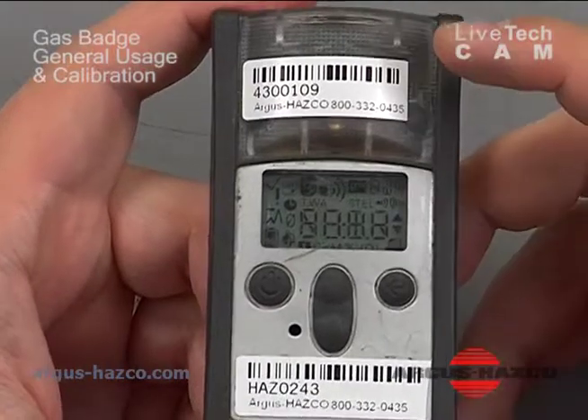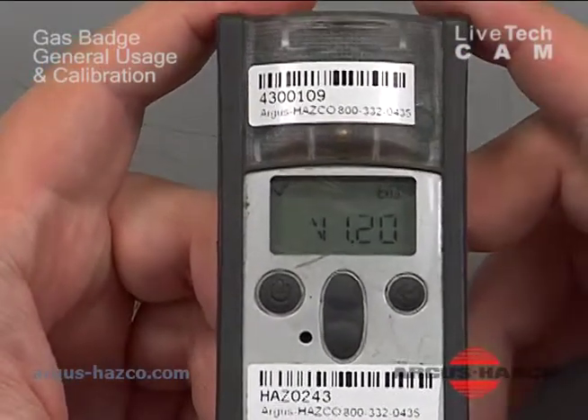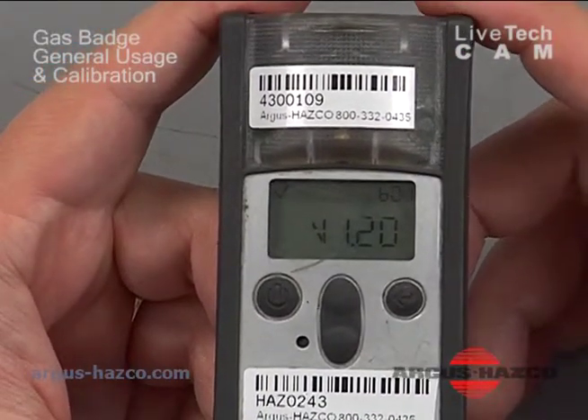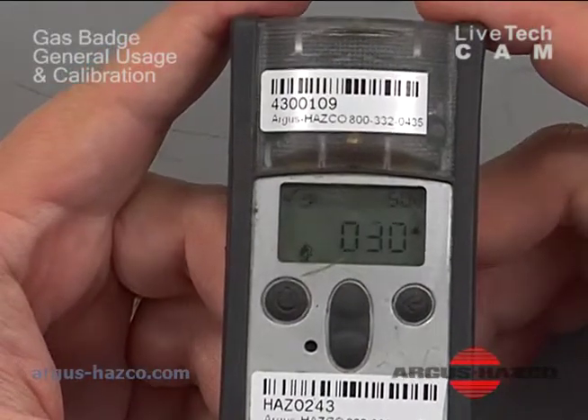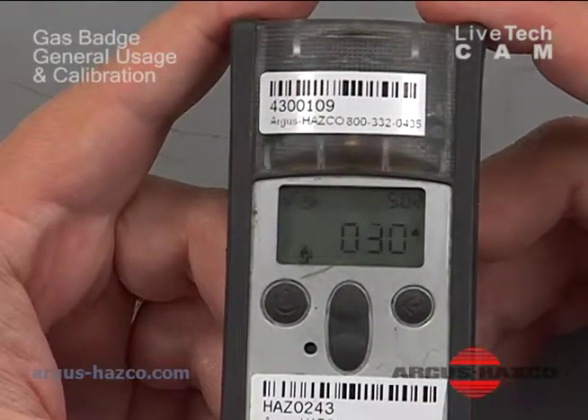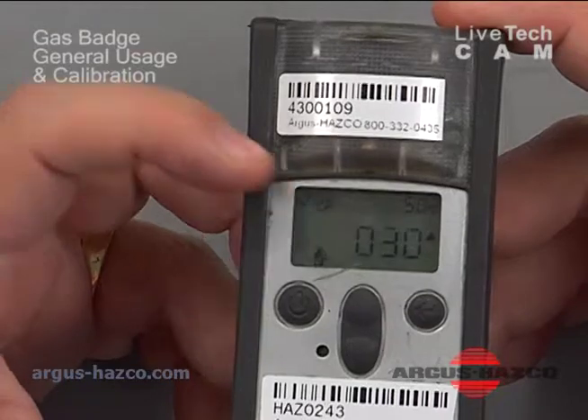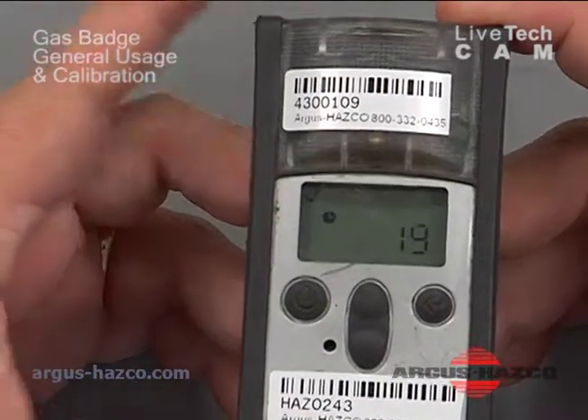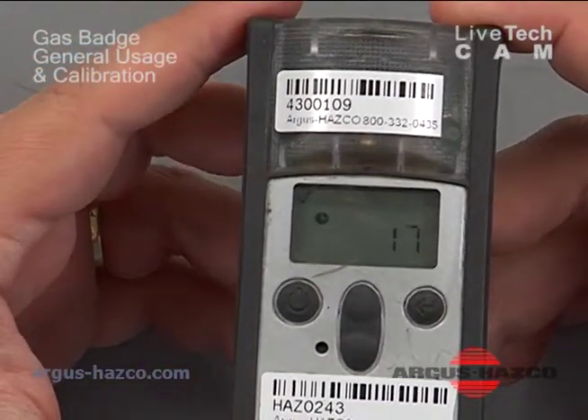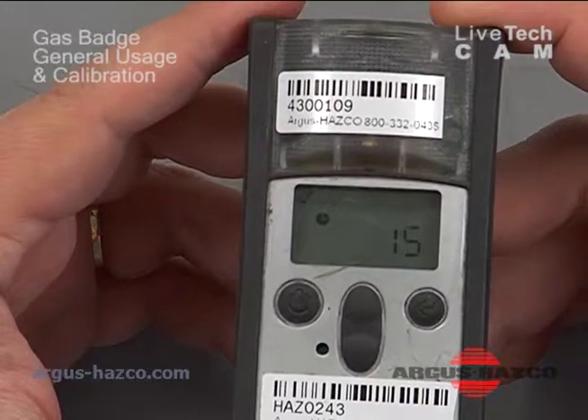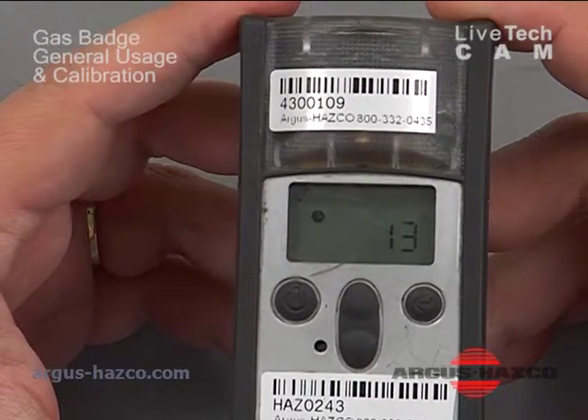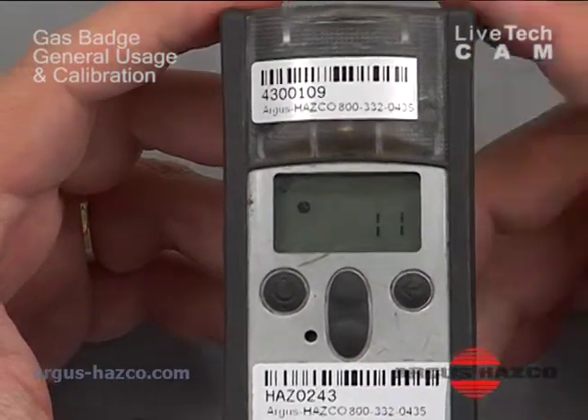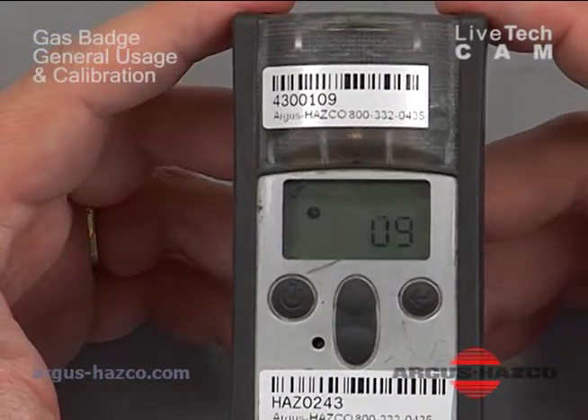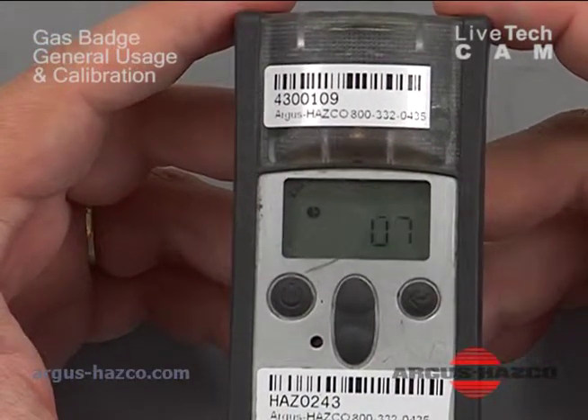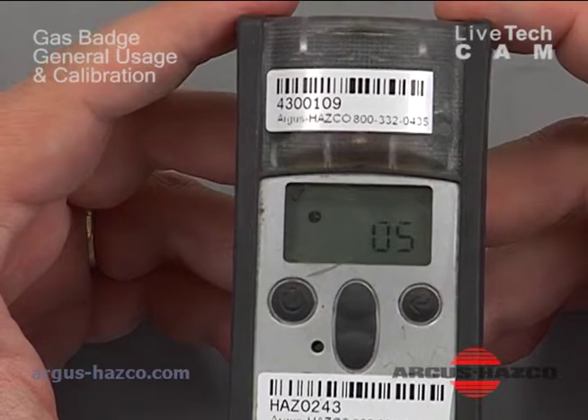It has visual, audible, and vibratory alert. It's telling you the software version. And here it's telling you it's got 30 days until its next calibration. You'll see the calibration, the 30 days up there telling you it's got 30 days. It's going to count down from 20 seconds, and it's ensuring that it's getting a signal from the sensors and there's no failure there electronically inside the instrument. If there is, it would fail at the end of this countdown and indicate that on the display.